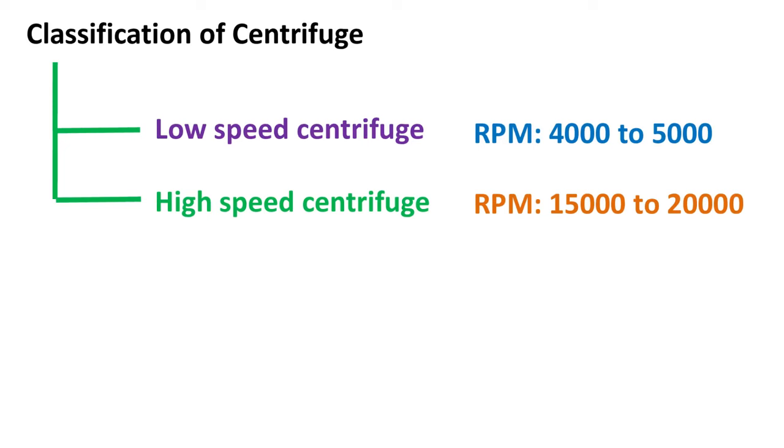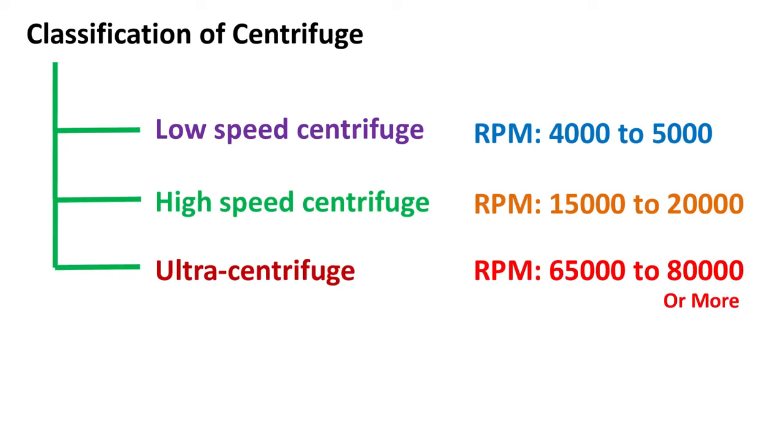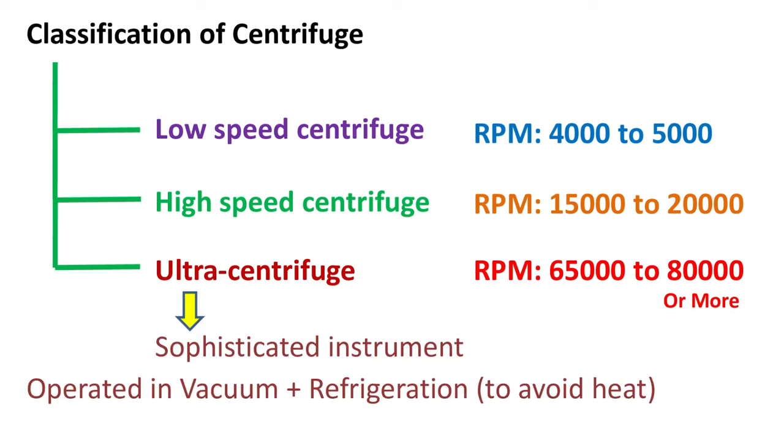On the other hand, ultracentrifuge can operate at maximum 65000 to 80000 RPM or even more. Ultracentrifuge is a sophisticated instrument which is operated in vacuum along with refrigeration to control the heat generated at such high RPM.